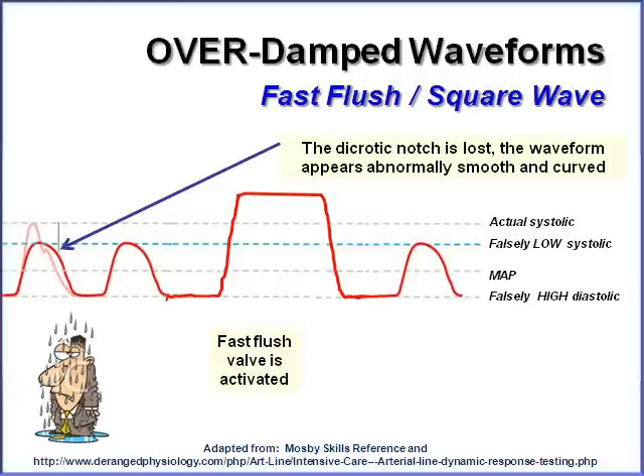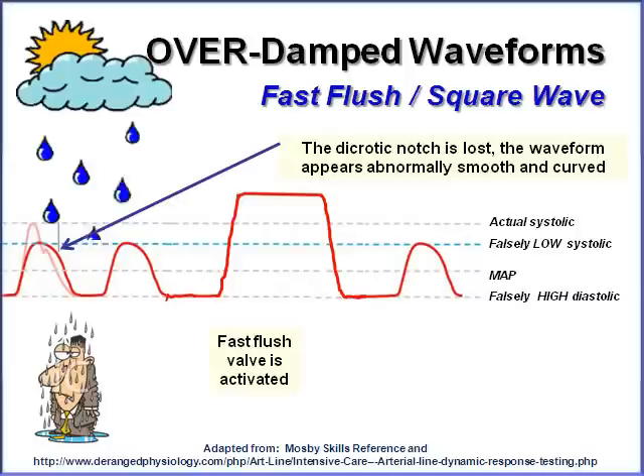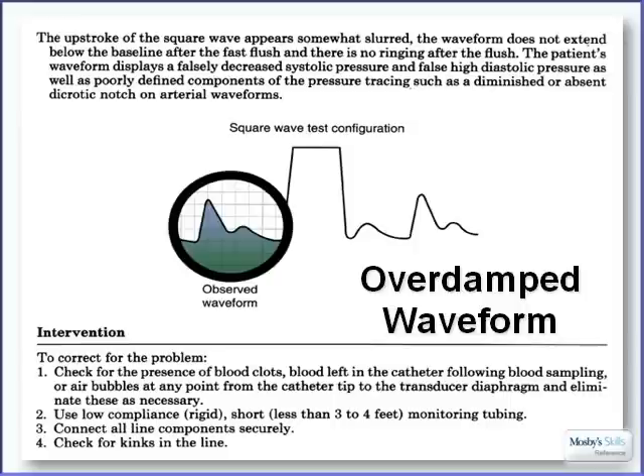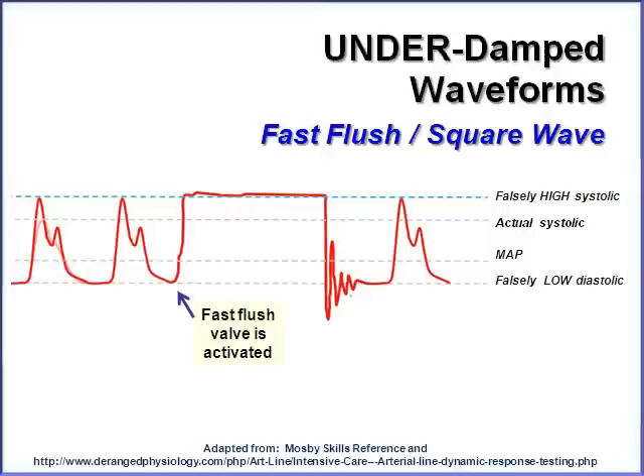Overdamped versus underdamped can be a difficult concept. Think of it this way: if I walk out in the rain and get my hair wet, my damp hair is going to go flat. So the waveform is getting rained on, causing it to dampen or squish down — you have none of the oscillations seen in an optimally damped waveform. In another example of an overdamped waveform, there are no oscillations and it's slow — not a snappy square, but slow to go up and slow to come back down.